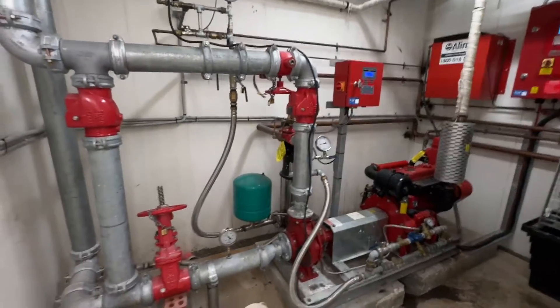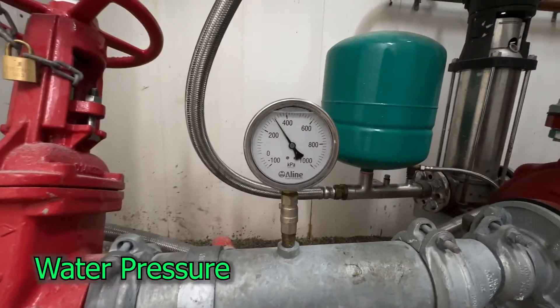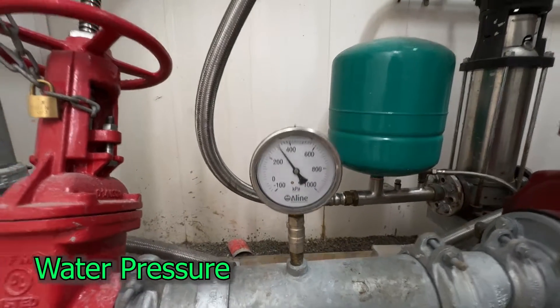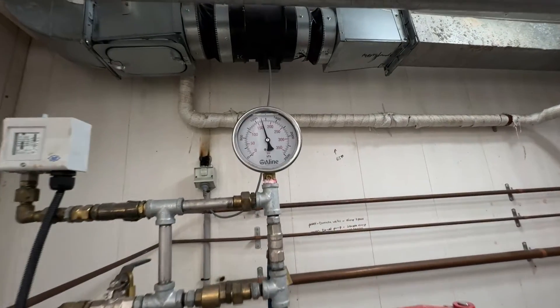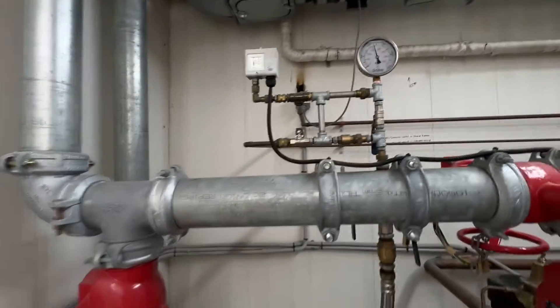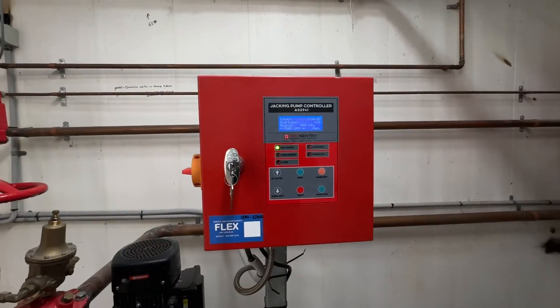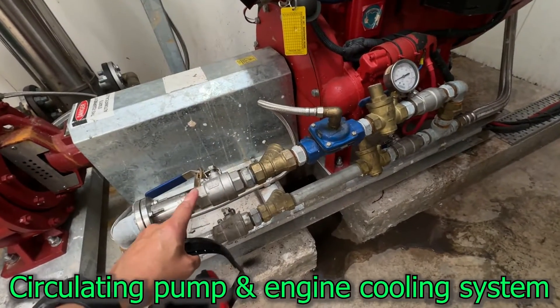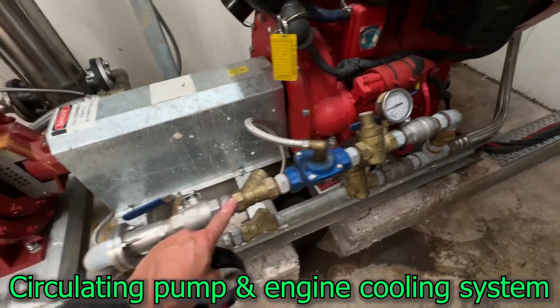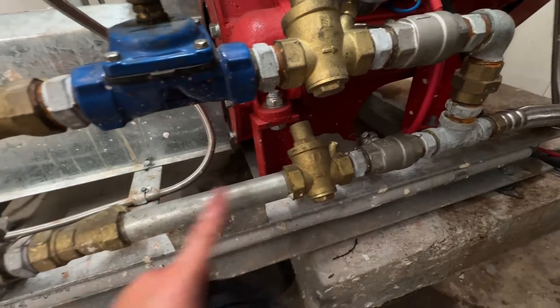First, check the following: do you have water in your tank? That will be your suction pressure, and that is your discharge pressure — also the installation pressure. This is your jacking pump. This is your cooling system for the engine. These two valves are on, and these two are off — that is the bypass.